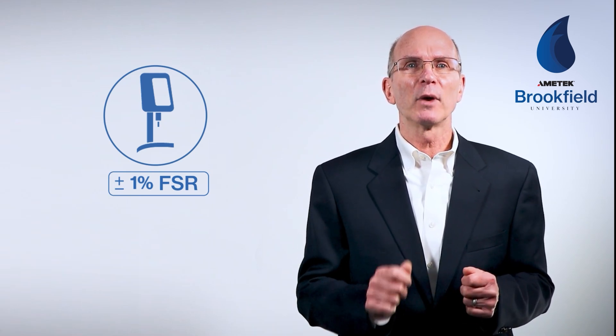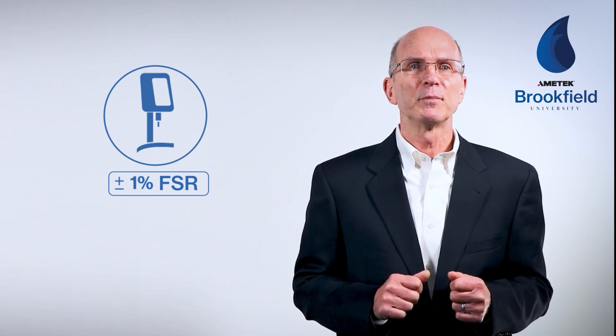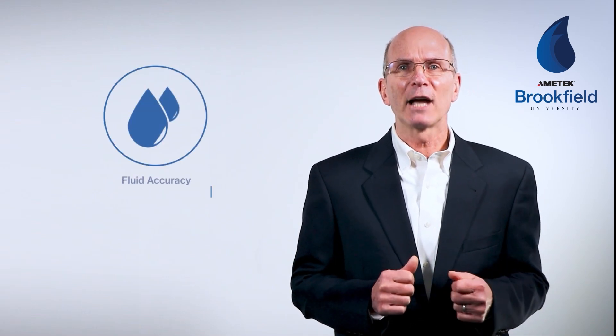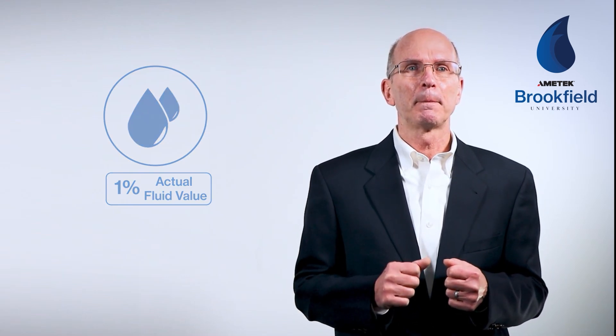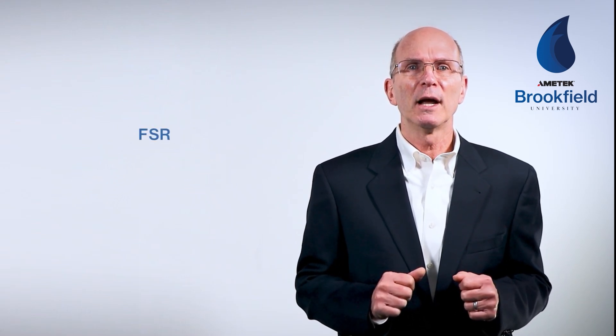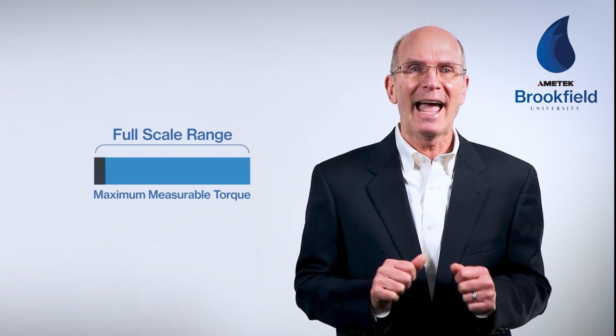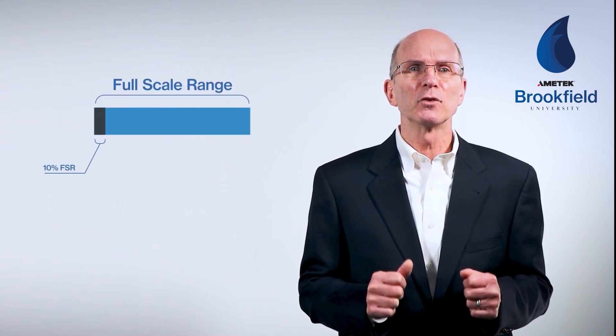AMETEK Brookfield states that when using standard spindles, the instrument accuracy is plus or minus 1% of the full-scale range in use. Full-scale range, or FSR, is determined by the spindle, speed, and spring range of the instrument. You must also consider the accuracy of the viscosity standard — the fluid accuracy is also 1% of the actual fluid value as stated on the jar and certificate. The FSR is 100% torque and the maximum centipoise value measurable; we can measure down to 10% torque accurately, so the minimum viscosity is 10% of the full-scale viscosity value.